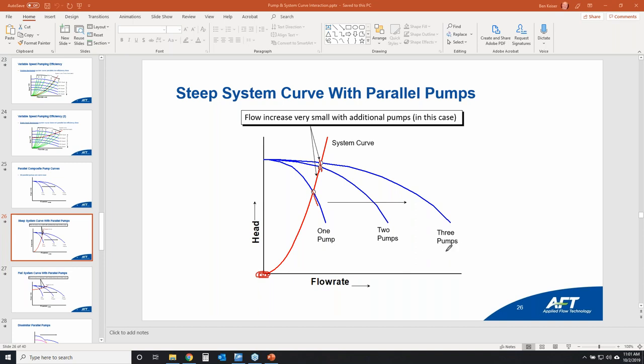And that's very similar to the Flowserve case study that I showed. In the original operation of that Flowserve brine injection system, they had five pumps in parallel and they were operating several at the same time. Well, when they're operating several at the same time, each individual pump by itself was operating at a really low flow rate, really, really far away from its best efficiency point. So what did Flowserve do? They figured out different combinations on which pumps they should operate and which ones they shouldn't, and they closed off various flow paths where they only ran maybe one or two pumps at a time, and that's how they were able to get their pumps operating at a much higher proximity to their best efficiency point.